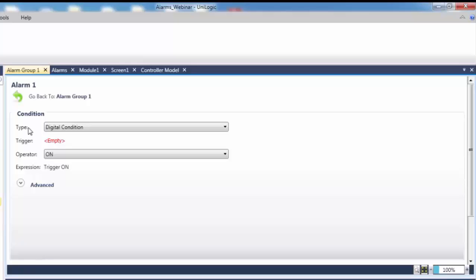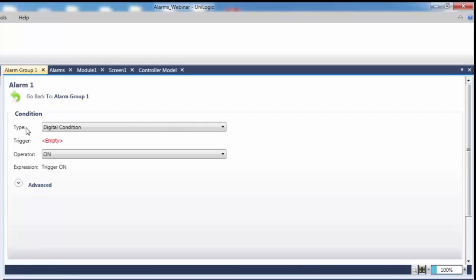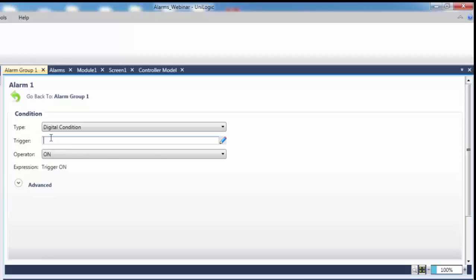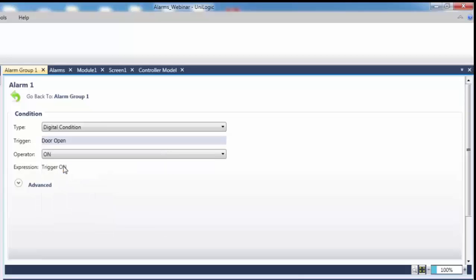Let's define an alarm for when the door is open. The door on our HMI is tied to the door open bit. When the door is open, this bit is on. For this reason, we have selected the door open bit as our trigger and our operator as on. That way, when the door open bit becomes on, our alarm is triggered.